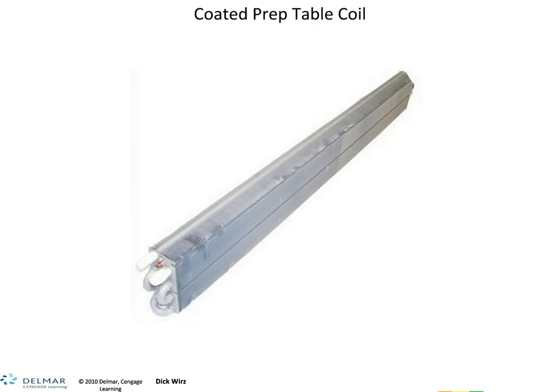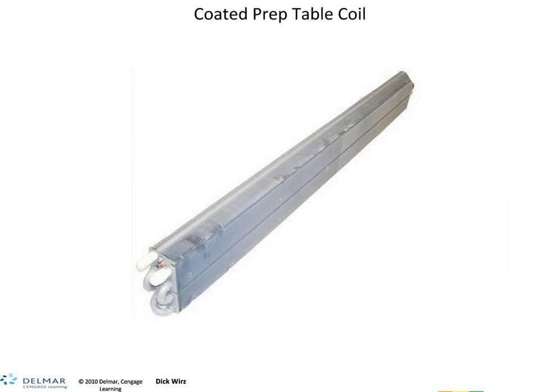The coated prep table coil is used in sandwich and pizza prep tables where product is kept in canisters and the sandwich is made right there on top of the cooler. These are coated with a special coating because you usually have tomatoes, ketchup, and other vegetables in there. The acids, especially from the tomatoes and ketchup, really eat away at the coil. So these are coated to protect the copper and the aluminum fins.